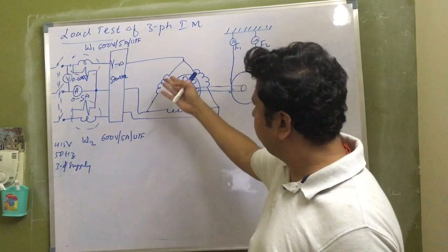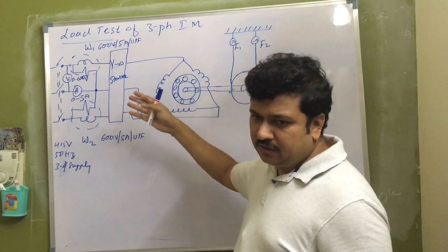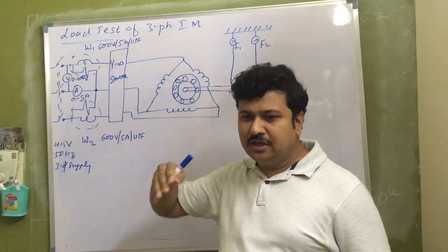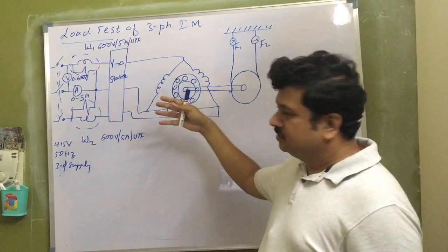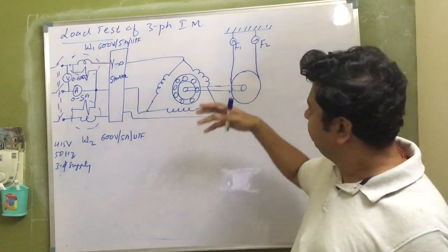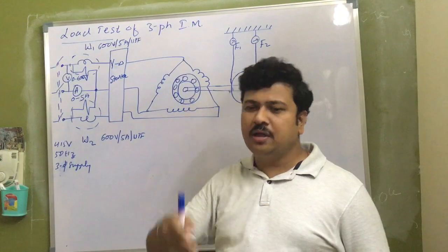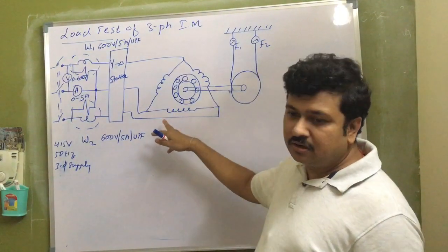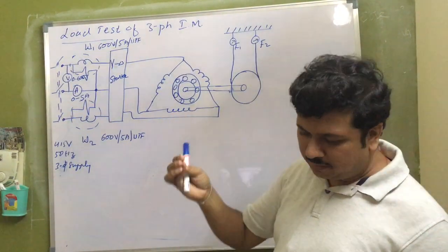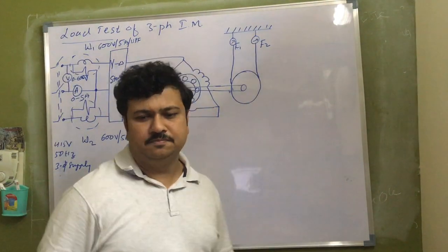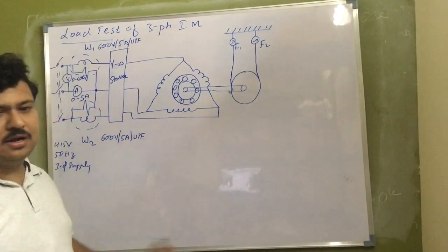It is a 4.8 ampere current rating, and if I see the current at full voltage, that is ISN, short circuit current at normal voltage, it will be not even 5 to 6 times, it is around 20 to 30 times larger than the load current, which will damage the stator winding immediately. Within no time my stator will get damaged.